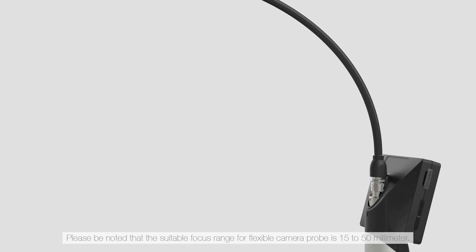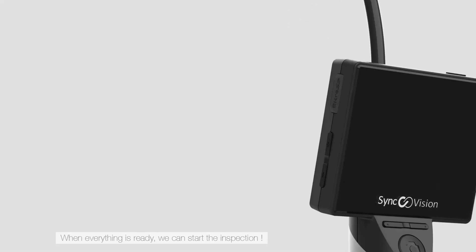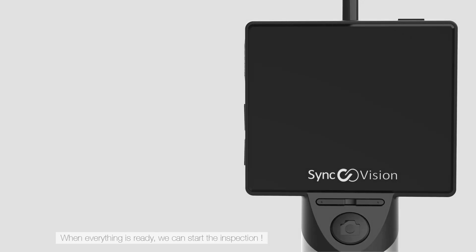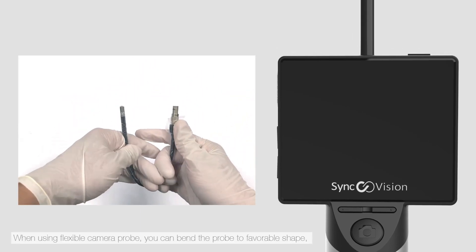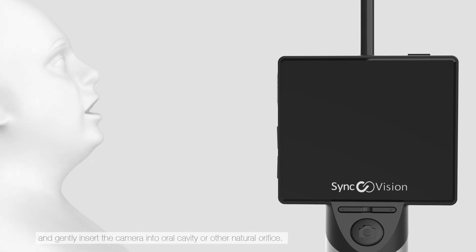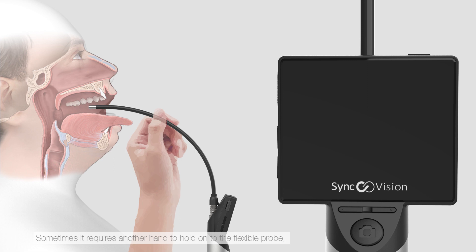Please be noted that the suitable focus range for flexible camera probe is 15 to 50 mm. When everything is ready, we can start the inspection. When using flexible camera probe, you can bend the probe to favorable shape and gently insert the camera into oral cavity or other natural orifice. Sometimes it requires another hand to hold onto the flexible probe to ensure steadier control and better aiming.